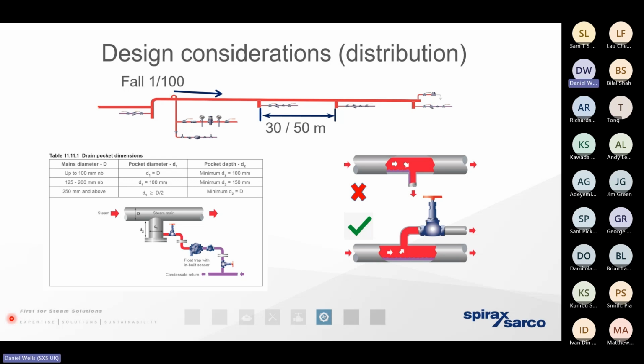Other good practice: we want to ensure that we've got a rise and fall in the distribution pipework, as you can see at the top of the page. The fall in the pipework needs to be in the direction of steam flow. That means we've got the movement of the steam and gravity helping the condensate move to a well-designed and well-engineered steam trapping station. That's where the condensate can drain away and the steam can remain in the infrastructure. Another best practice is taking the steam away from the top of the distribution pipework, not the bottom and not the side, because that way we run the risk of flooding the heat exchanger with an excess of liquid condensate that simply doesn't have enough heat energy present within it.